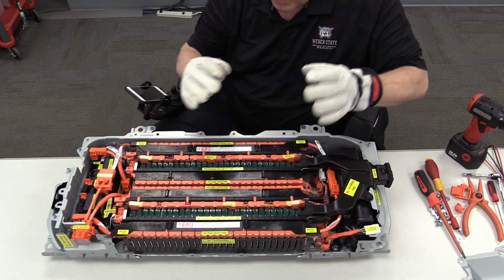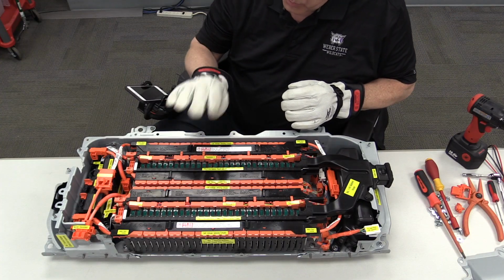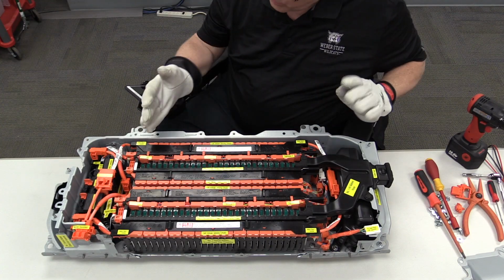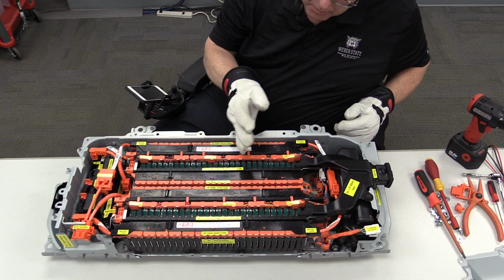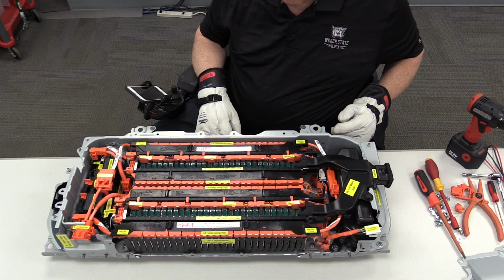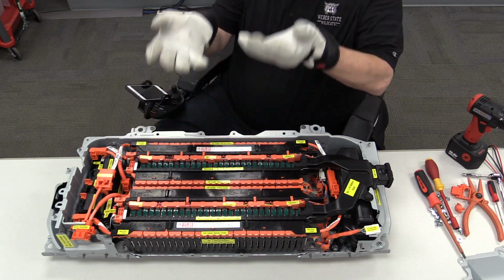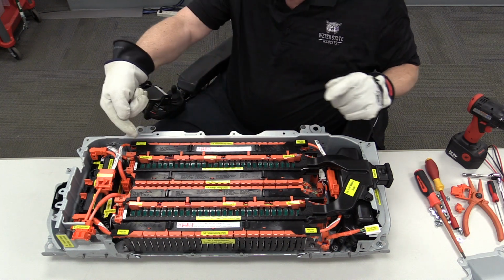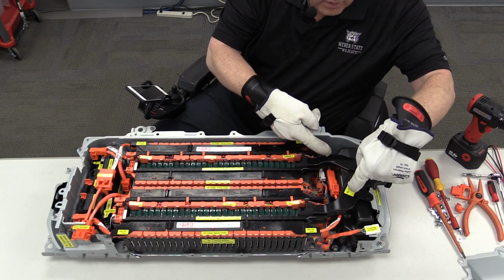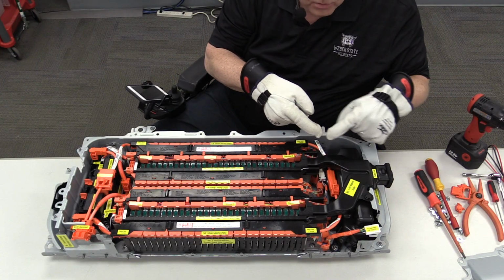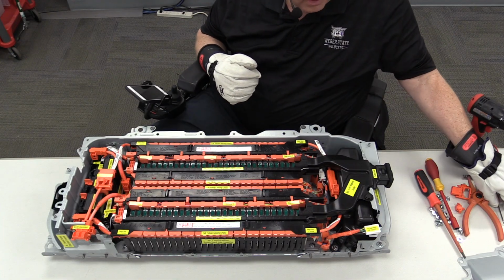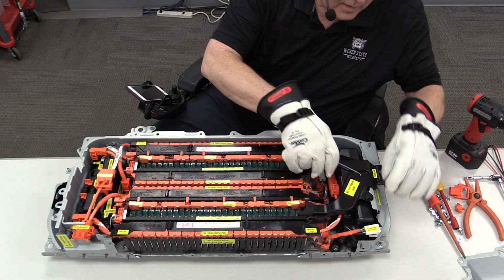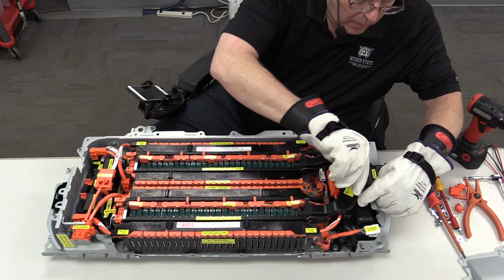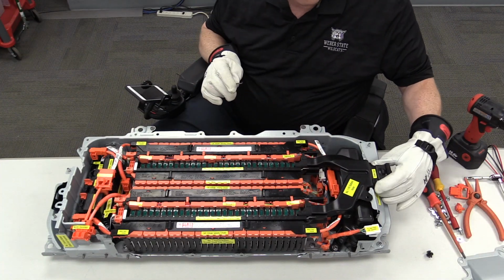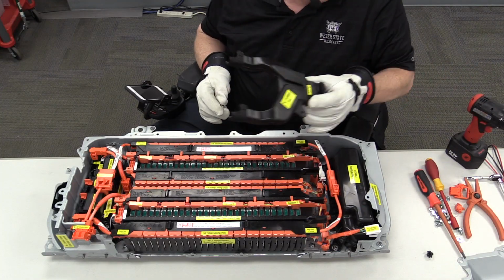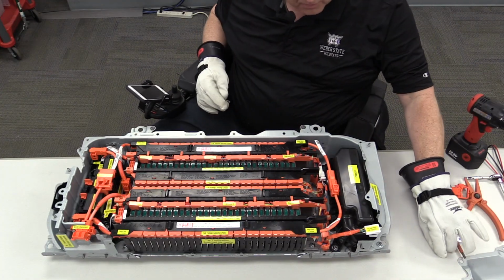We have 2 separate battery stacks here of 103.6 volts each. There are 28 3.7 volt lithium-ion battery cells in each stack. So the air will go in under the stack, come up through the stack, get sealed against that upper cover, and then pushed out over here through what they call the number 1 HV battery hose, or an outlet duct. And so we can take this duct off. There's just a little clip here holding it on, and it comes right off. So we'll set that off to the side.